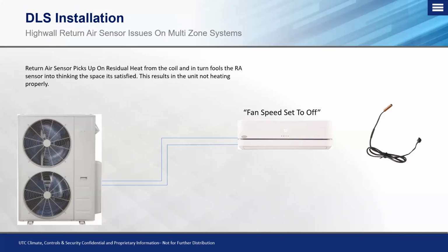Okay, so what we need to do is not only program that fan speed to shut off after a set point, we need to relocate the return air thermistor to the right side of the unit. Okay, and again, that's to make sure when we shut the fan speed off that we're maintaining and reading an accurate room air temperature so that the system functions to the customer's expectations.